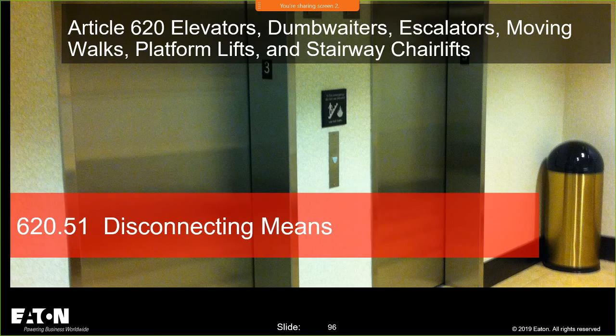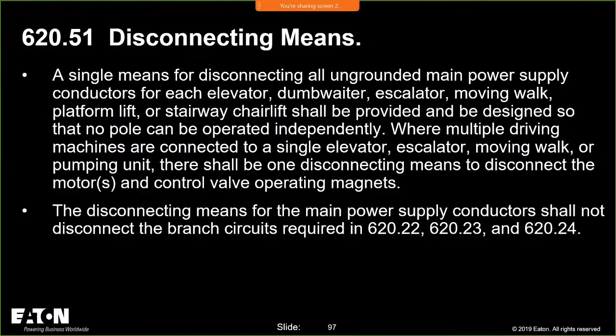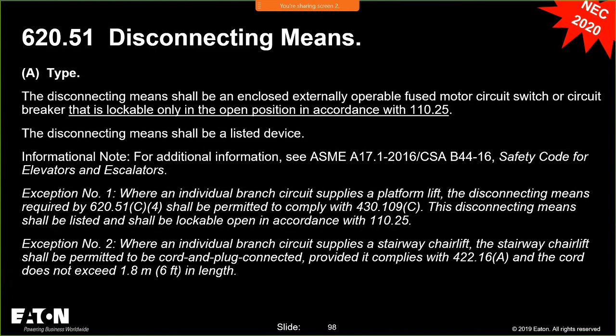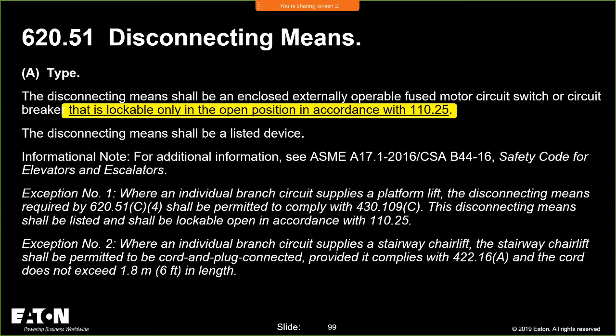Now here's another interesting one, because we had a debate, and I don't think I covered this one, but I had a debate over in Massachusetts with an inspector at one point. They talk about in 620.51 a single means for disconnecting all ungrounded main power supply conductors for each elevator. It has to be there, etc. And this is the language that they changed. That is lockable only in the open position. That means that if you have two holes in there, one where you can lock it in the open position and one where you could lock it in the closed position, this is like the only area that I'm aware of in the National Electrical Code where that would be prohibited. It can only be lockable in the open position.